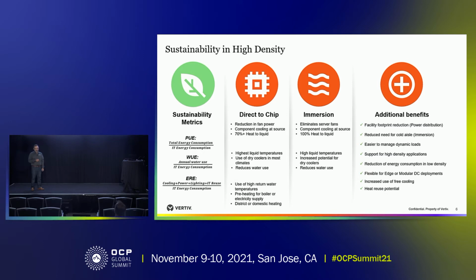You can also look at immersion to accomplish this. I mentioned the 70% that goes into the liquid on a cold plate design. Well, in immersion, you get the rest of that covered in the full envelope of the server, giving you a nice heat capture to the fluid.